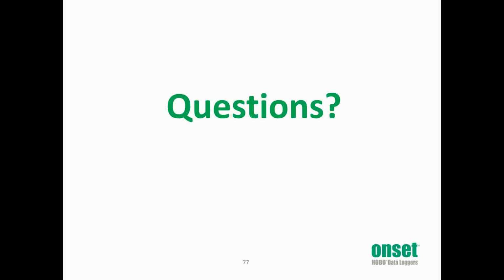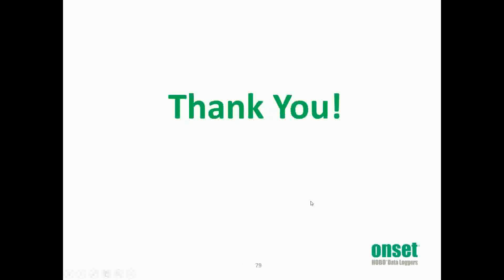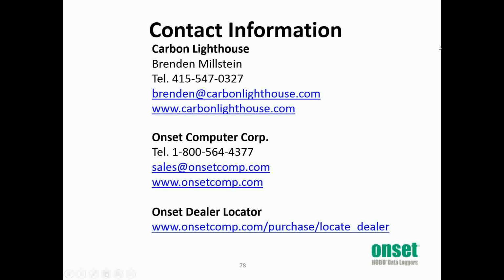Can you do stealth projects when acquiring interval electricity data? Doesn't that require temporarily turning off the breaker you'll be monitoring? No, it does not, and you can absolutely do stealth projects with interval metering. We're lucky in that we often work with Pacific Gas and Electric and other California and Oregon utilities, where we get to download the interval meter data directly from the utility. You can also put metering equipment in panels while they're live, depending on the voltage and your state regulations, but make sure you have a qualified professional doing that with proper safety equipment.